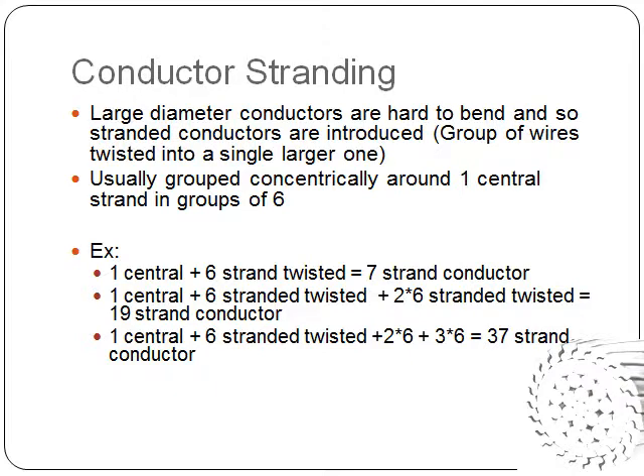If you need another layer, you add two times six, which is twelve, plus the original seven, which makes nineteen. And if you want another layer after that, you add eighteen strands, giving you a thirty-seven strand conductor, and so on as it continues.